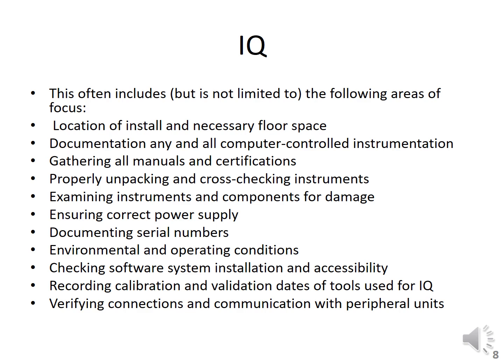Now, before starting the installation and during installation, you must know that if there are any manuals or certifications which are being provided by the manufacturers or the company or the vendor providing you the machine, any manuals, any certifications which are relevant to the machine, the equipment, you must have all of those, and you must gather all of them, and you must keep them in a proper way, right? Properly unpacking and cross-checking the instrument. This is important.